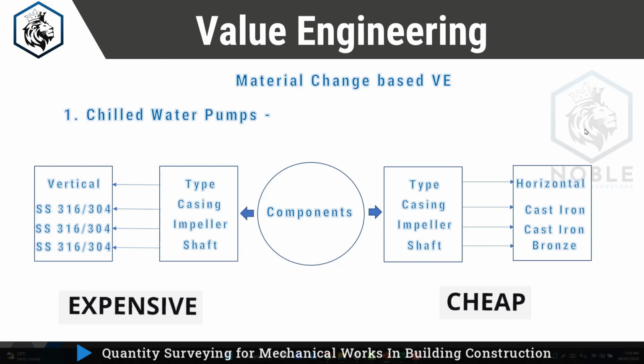Doing this value engineering, you will save almost 25 to 30% of the total price. If your chilled water pump costs 100,000 dirhams, with this value engineering you can get the same pump with the same functionality for almost 60 to 70,000 dirhams. So just keep in mind: the cheaper option is horizontal type, cast iron impeller, cast iron casing, and bronze shaft. If you see any of this, you can replace it and save almost 30 to 40% of the cost of this item.